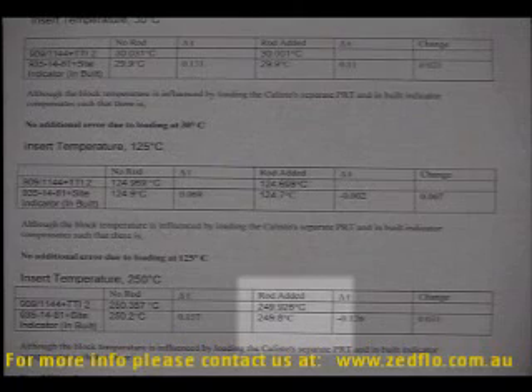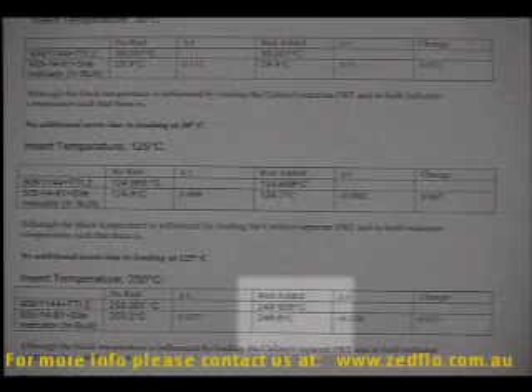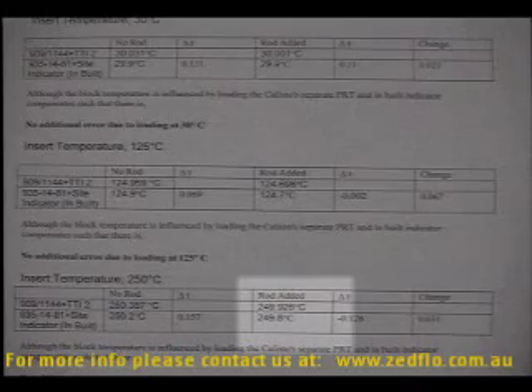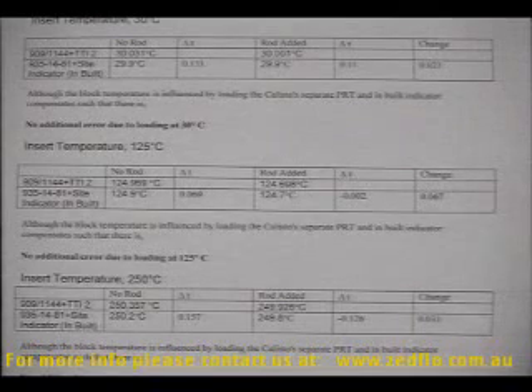This is a solid rod of either copper or stainless steel, with a diameter of 8 or 9 millimeters, and it protrudes from the insert for about 200 millimeters. Eventually it gets to room temperature, and this drags heat out of the insert and changes its temperature from the no-load situation to the loaded situation, about 0.43 degrees Celsius. Our built-in semi-standard connected to our indicator is also going to change in temperature, and this compensates for the loading effect. If you relied only on the controller indication, then that 0.4 degrees Celsius would be a loading error, which would have to be added to the uncertainties.